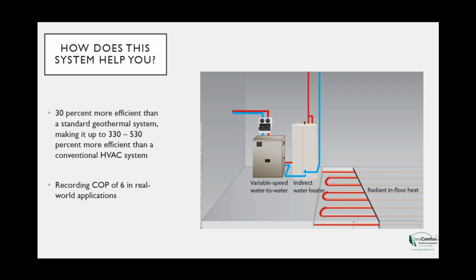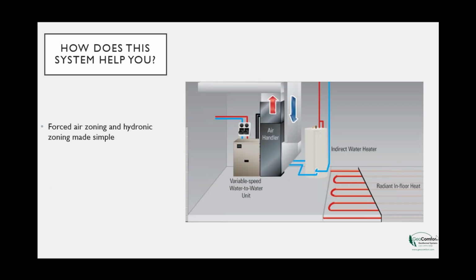It does it the complete opposite. It slows down, it reduces the temperature, which just increases the efficiency. And most of the year, that's where you're going to be running, in those higher COP ranges. Only the worst or the coldest days of the year are you going to be running those high speeds and high temperatures.